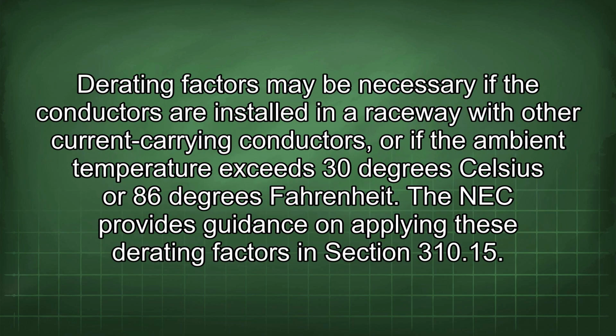Derating factors may be necessary if the conductors are installed in a raceway with other current-carrying conductors, or if the ambient temperature exceeds 30 degrees Celsius or 86 degrees Fahrenheit. The NEC provides guidance on applying these derating factors in Section 310.15.